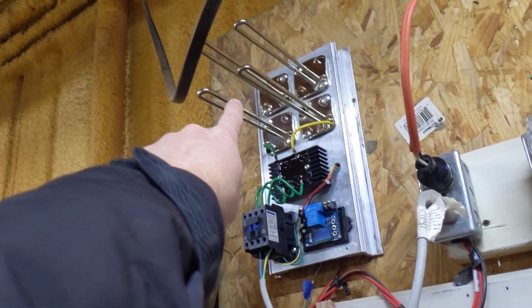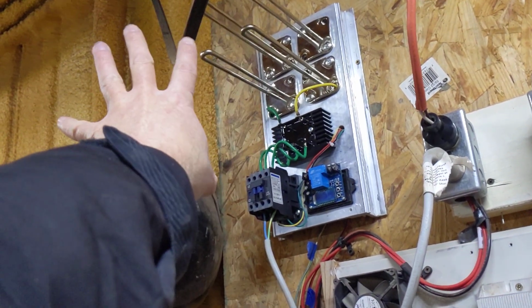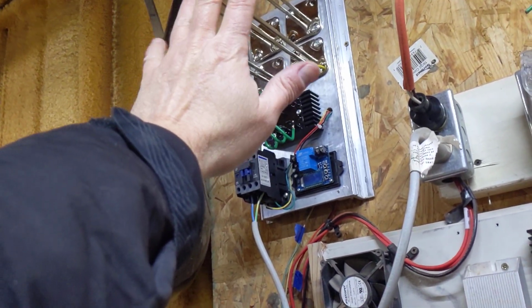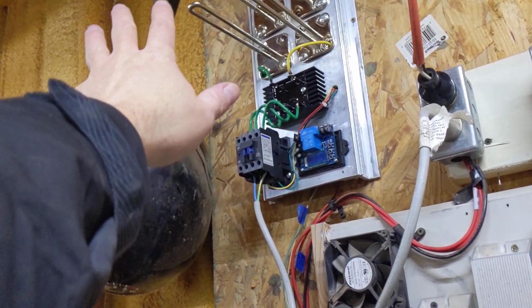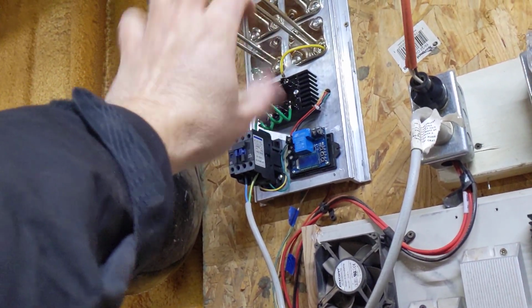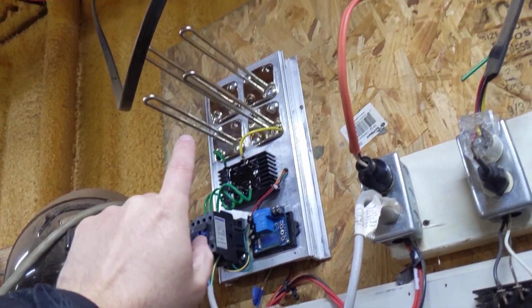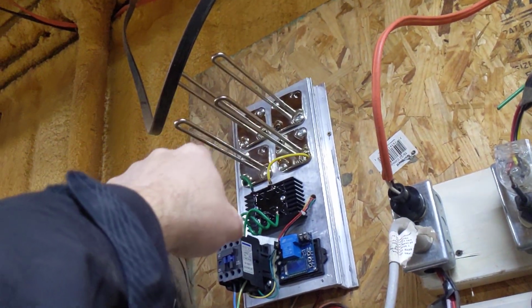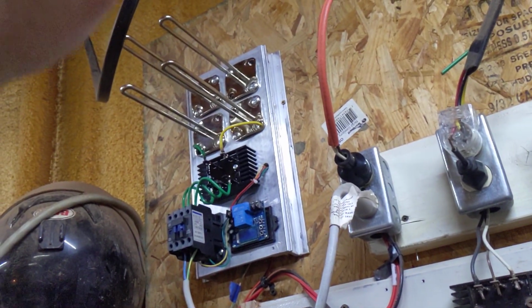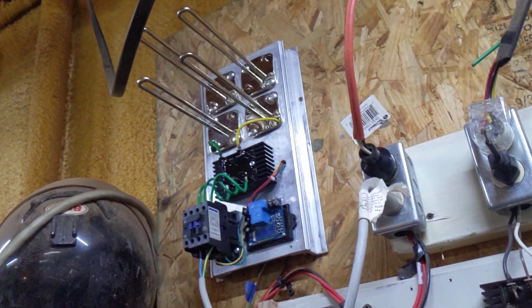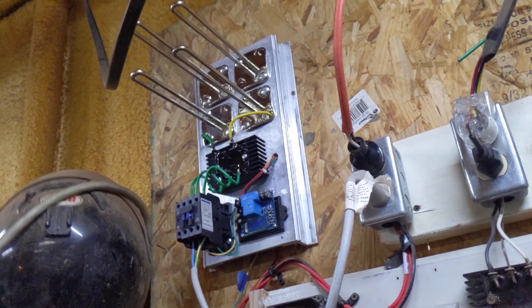These are all 120 volt, 1500 watt elements, which should put it right around 9.5 ohms. They actually ohmed out a little bit above that. Running the 4 in parallel brings my ohm rating down to about 3.5.